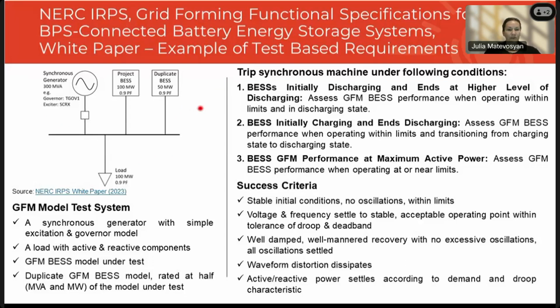And so there are these 3 tests that are applied. You trip the last synchronous machine under the 3 following conditions: where the battery is initially discharging and ends up at a higher level of discharging when the synchronous generator trips. Then the BESS is initially charging and it needs to switch over to discharging as the synchronous generator trips. And then if the BESS is operating at its maximum active power, and then the synchronous generator trips, what happens then?